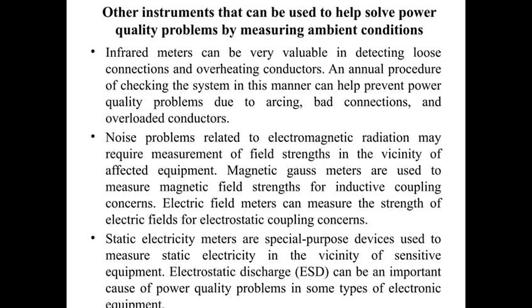Noise problems related to electromagnetic radiation may require measurement of field strength in the vicinity of the affected equipment. Magnetic Gauss meters are used to measure magnetic field strength for inductive coupling concerns. Electric field meters can measure the strength of the electric field for electrostatic coupling concerns. Static electricity meters are special purpose devices used to measure static electricity in the vicinity of sensitive equipment. Electrostatic discharge, that is ESD, can be an important cause of power quality problems in some types of electronic equipment.